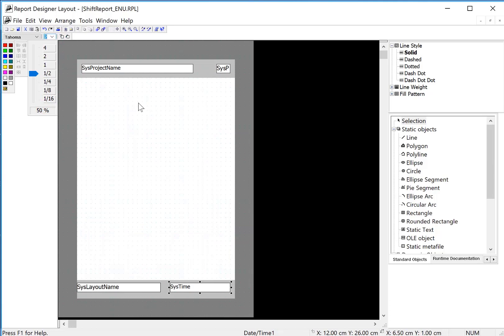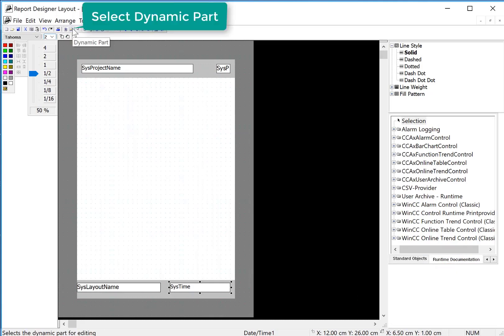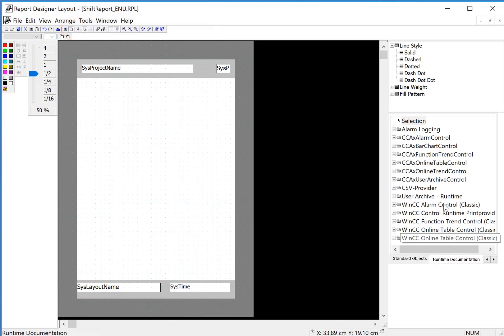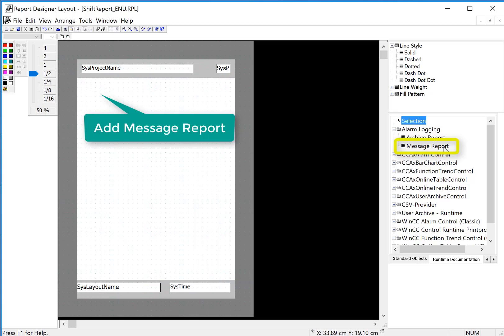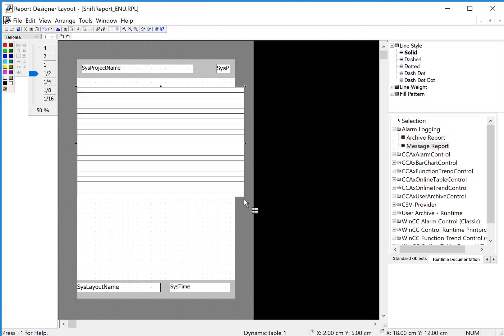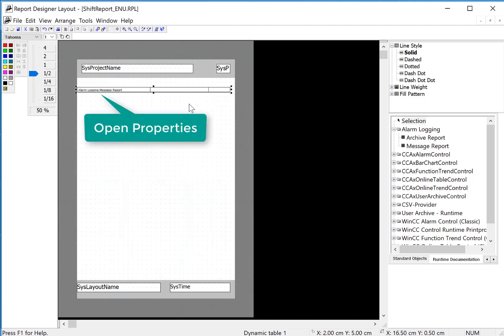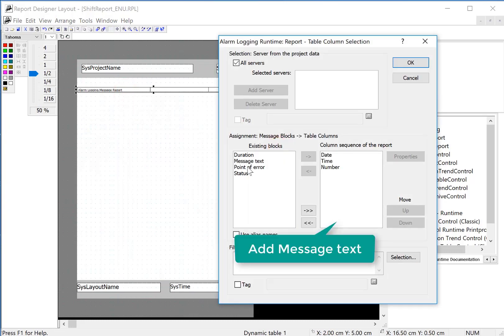Next I want to put process information from alarm logging and tag logging. We'll go to the runtime documentation tab and we need to be in the dynamic mode — these are dynamic objects. I'll go under alarm logging, and we have two things here: archive report and message report. Message report shows active alarms; archive report shows archived messages. So I'll choose a message report — these controls are self-paginating, they're going to grow to fit the data, so you don't have to make them big. We can just do one line, then double click to get to the properties. On the connect tab I'll go into selection, choose the blocks we want, and put message text there, then click OK.